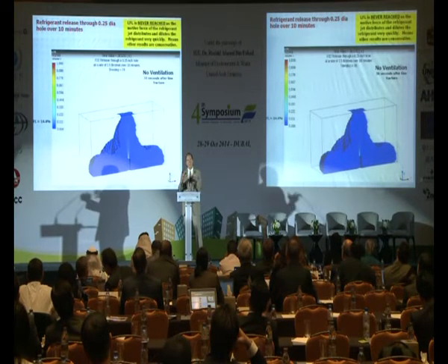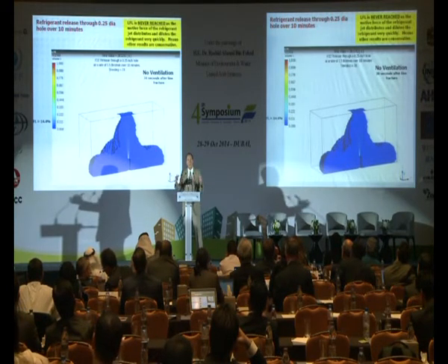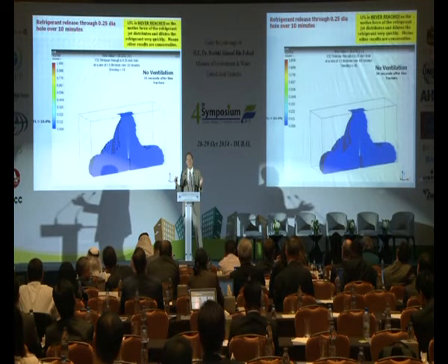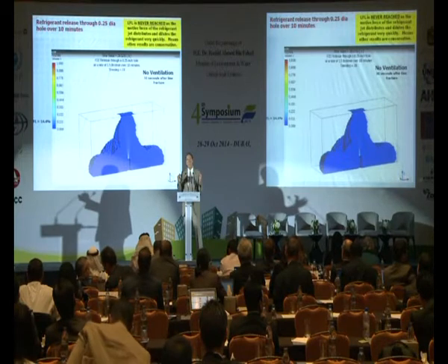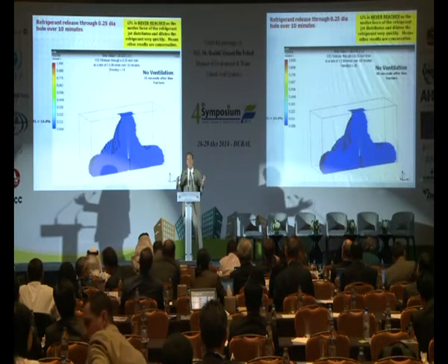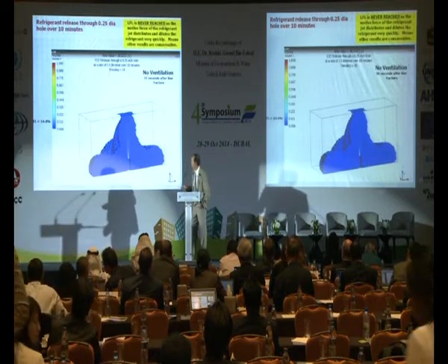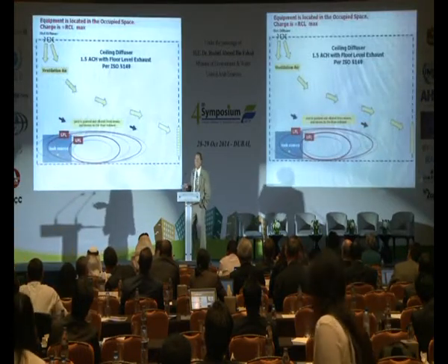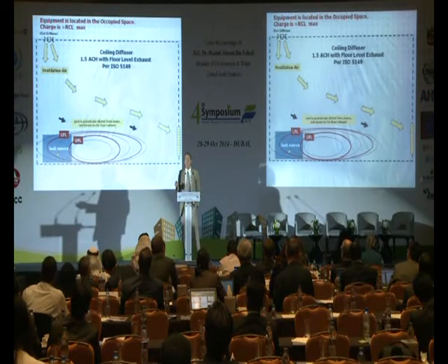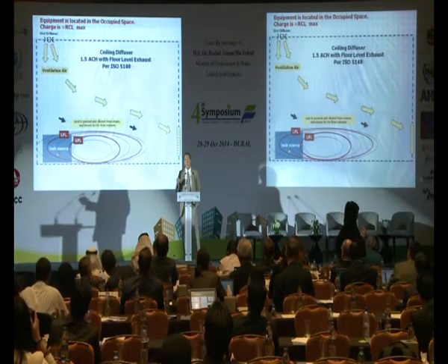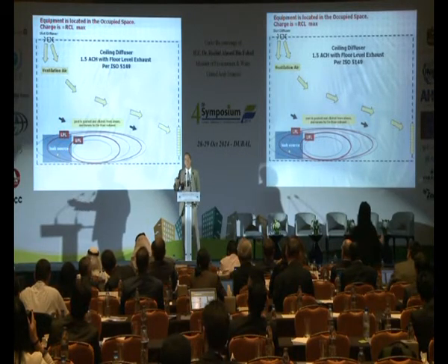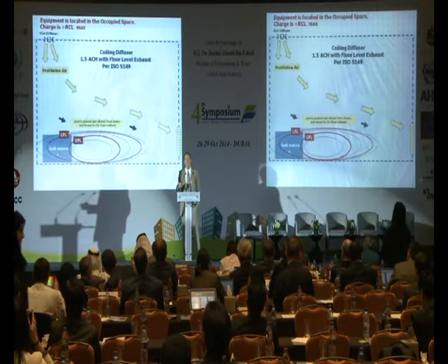Neither can you release the refrigerant instantaneously without some kind of a broken line, nor can you release the refrigerant unencumbered. There's almost always a cabinet with the equipment that's installed in the occupied space. So the answer is somewhere in between, but the point is the jetting effect is a very, very powerful motive force. So again, we move in the direction of safety.